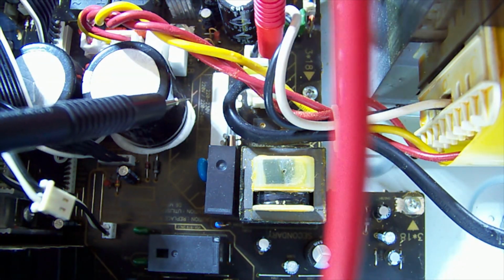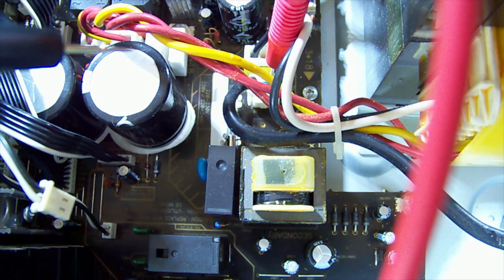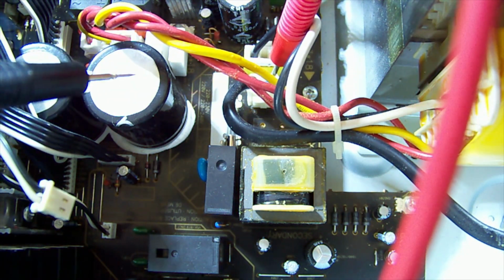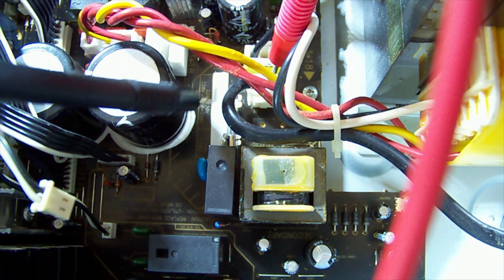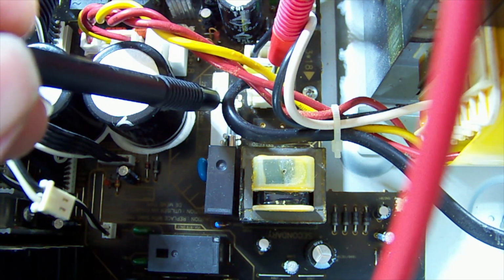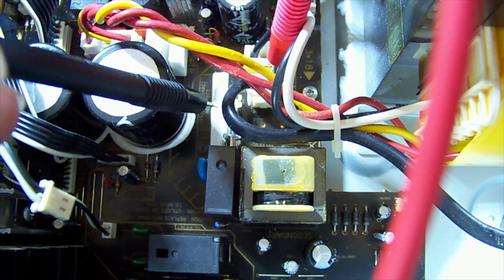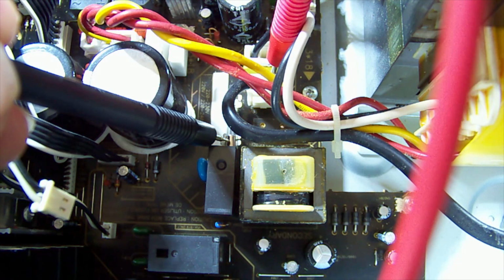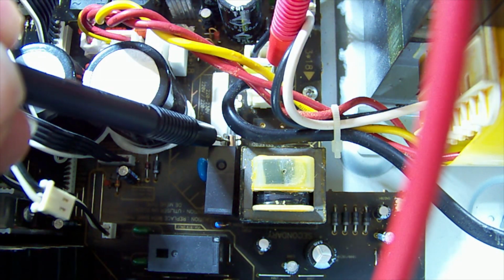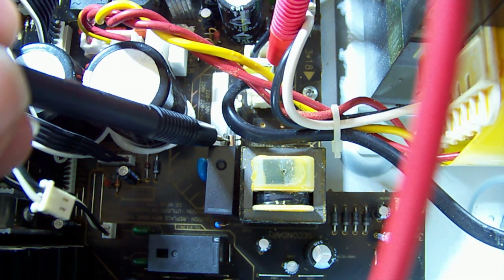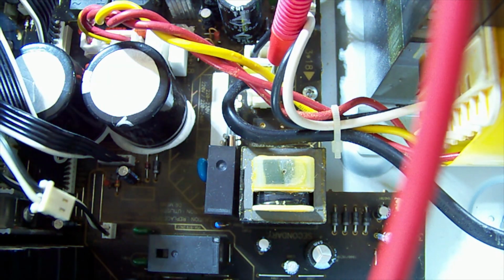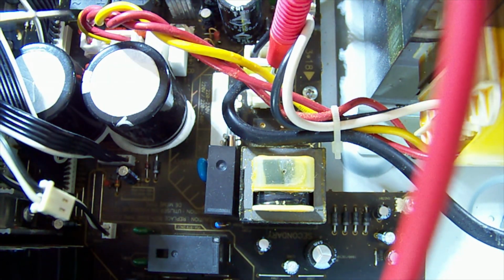So that's always going to be on the phase side, so one probe in neutral, our blue wire, and we'll check we've got 240 on one side of the fuse, 240 on the other side of the fuse. There we go. Well, it's actually 237 at the moment, so that's alright.